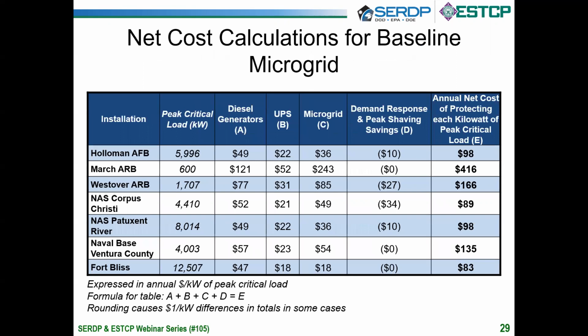You will see that the far right column here is the same as on the last slide. The formula to build it up is simple. Just add the cost in columns A, B, C, and D to get the sum in column E. That is, add the costs of a centralized set of new diesel generators with N+1 redundancy, the same assets Jeff described on the reliability side, new UPS, also with N+1 redundancy, the microgrid to control the generators, UPS and PV, and then column D, any savings you can obtain from these microgrid assets participating in demand response or peak shaving on electric utility bills.